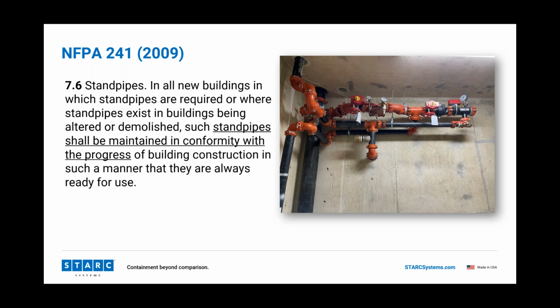Standpipes. I'll harp on standpipes just a little bit. The biggest thing here is that when you're building a new building, when you're building an addition, when you have standpipes in the building, the standpipes have to be maintained and ready to be used at all times. Okay. If not, you've got to coordinate with the fire department. The whole point of the standpipe, especially if you don't have an active sprinkler system, is that this is the line of defense, right? So the fire department has to be aware of the construction that's going on, and where the standpipes are not active has to be very, very clearly marked and communicated. I was just reading a case study this weekend about a building under construction that caught on fire and burnt to the ground, because the active standpipes would have prevented it. So this is something that happens currently too.